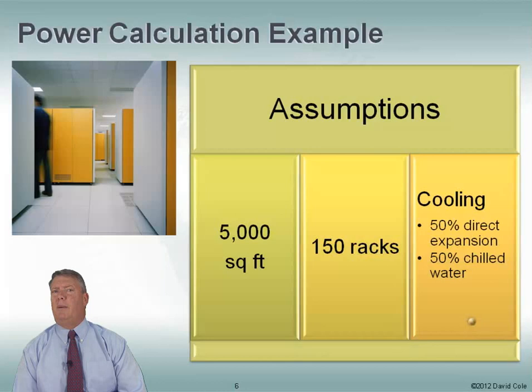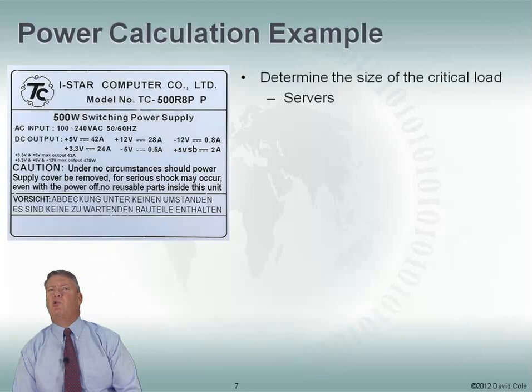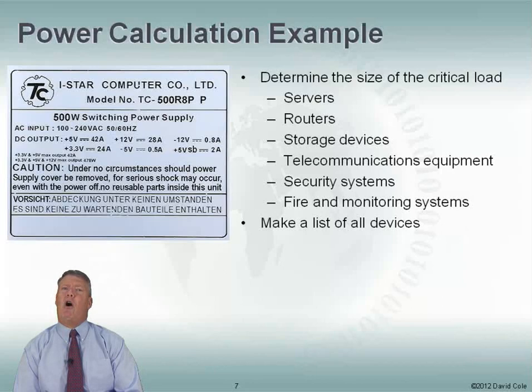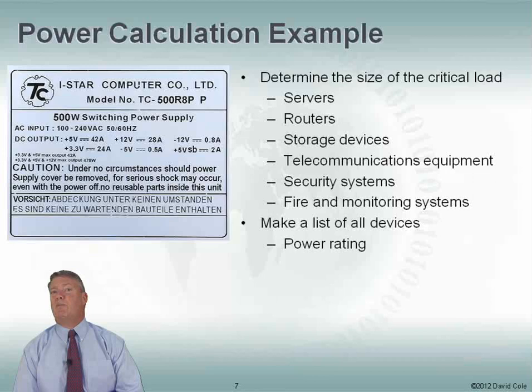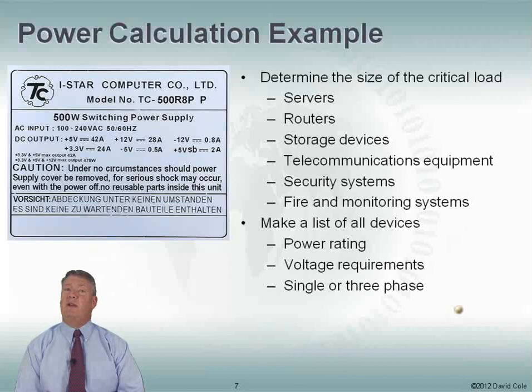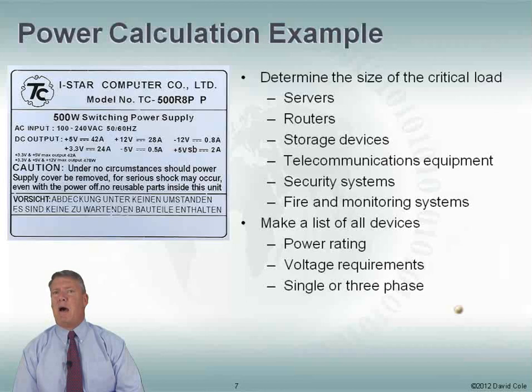First, we're going to start by determining the size of our critical load. What's in our critical load? Things like servers and routers, storage devices, telecommunications equipment, security, and fire monitoring — all of these are our critical load, the things we want to make sure are up all the time. We're going to make a list of all these devices, look at their power ratings — using manufacturer calculators rather than just nameplate values — and also their voltage requirements, including whether we need single or three phase power.